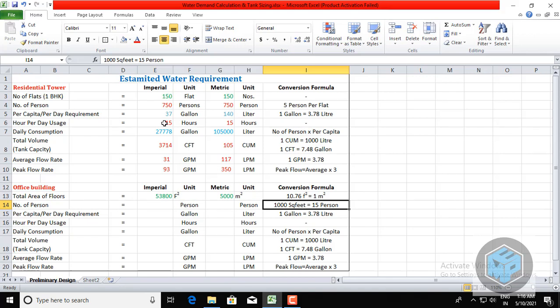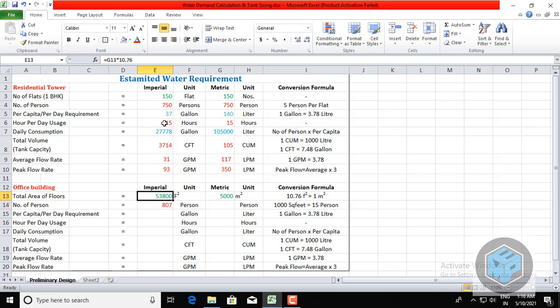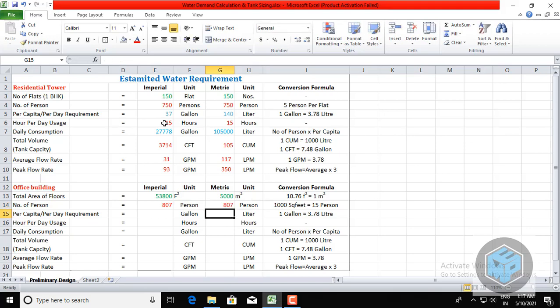Using the assumption of 15 persons per 1,000 square feet, the number of persons = total floor area ÷ 1,000 × 15 = 53,800 ÷ 1,000 × 15 = approximately 807 persons. This same figure of 807 total persons is used for both the Imperial and metric calculations.